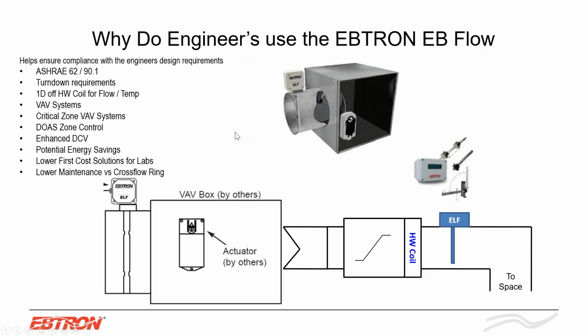And with all of our EBTRON units, again, there's no recalibration. So lower maintenance versus crossflow ring. You're never going to have to get in there and recalibrate these units. Once you install them, it's set and forget it.